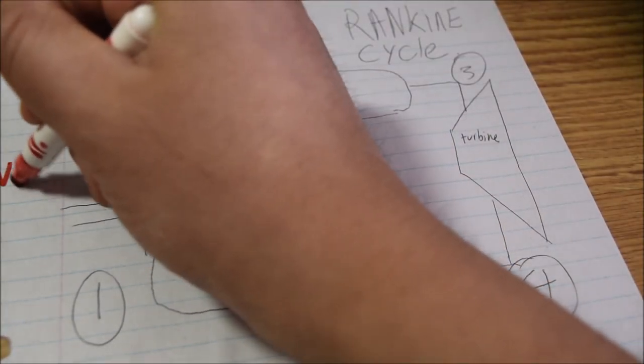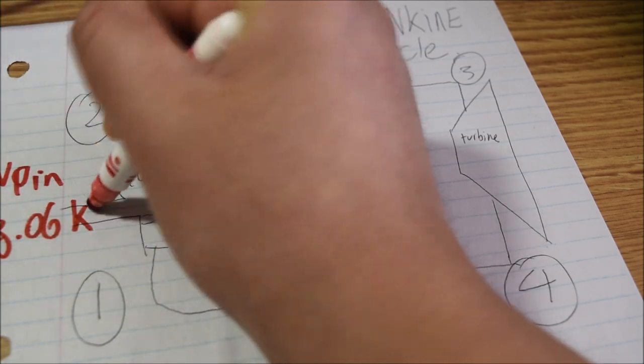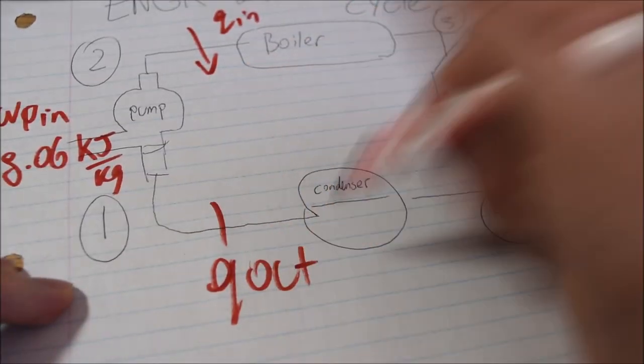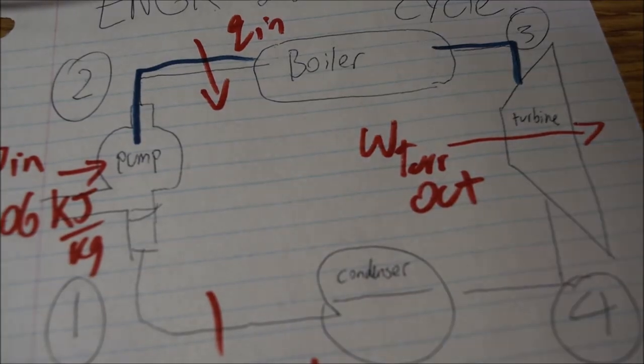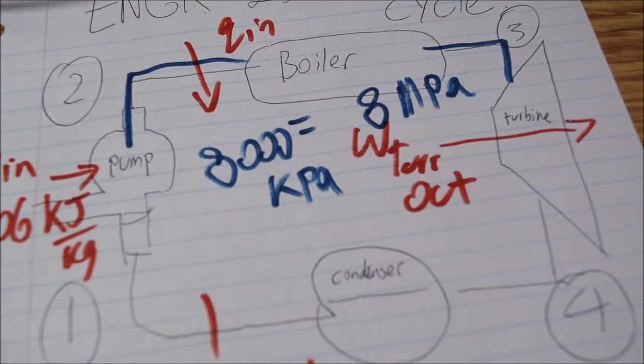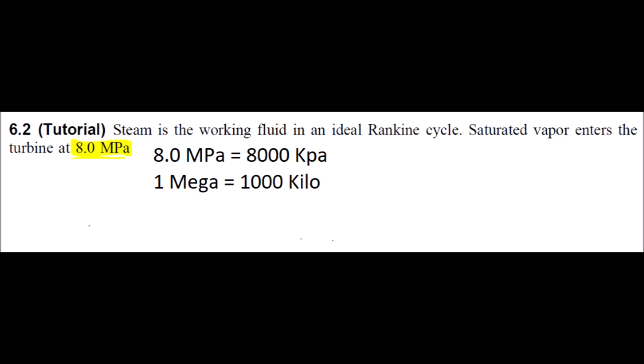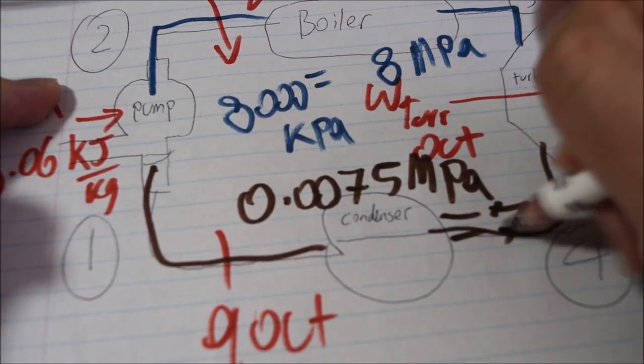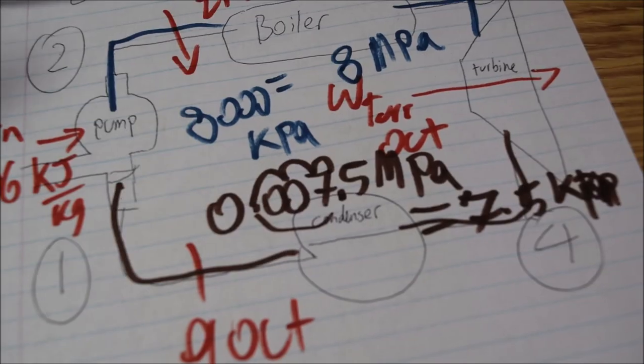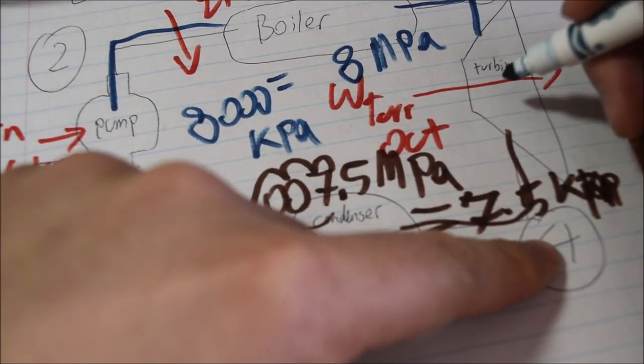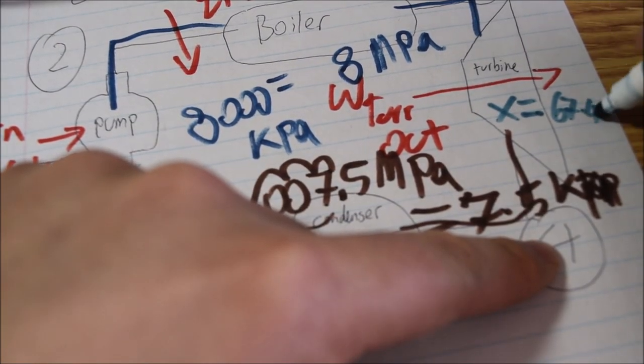From the problem, we know that the work of the pump in is 8.06 kilojoules per kilogram. Q in, Q out, and work turbine out. It is given that the pressure entering the turbine is 8 megapascals, equals 8000 kilopascals. The pressure exiting the condenser is 0.0075 megapascal, or 7.5 kilopascals. It is also given that the quality x equals 67.45%.